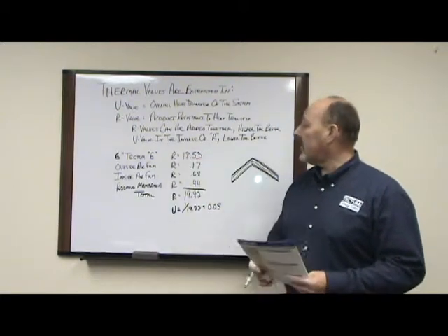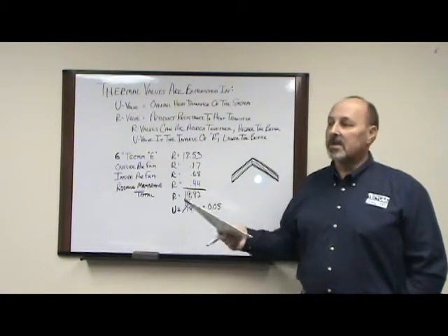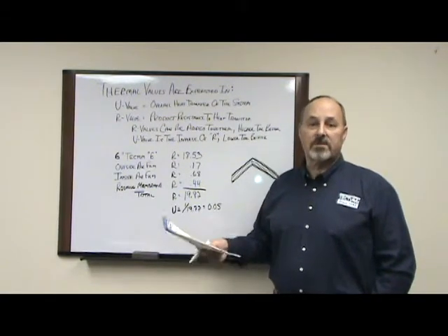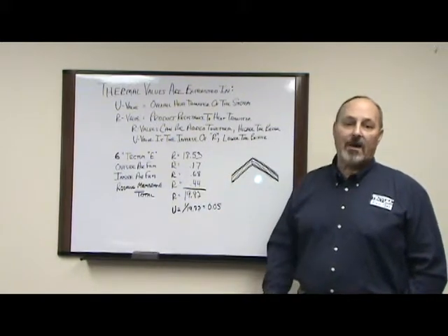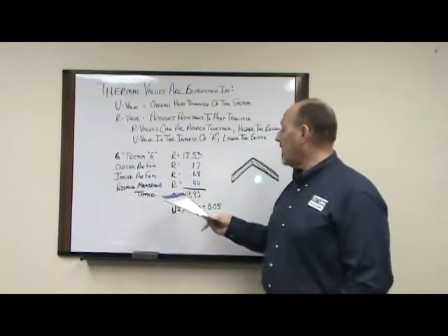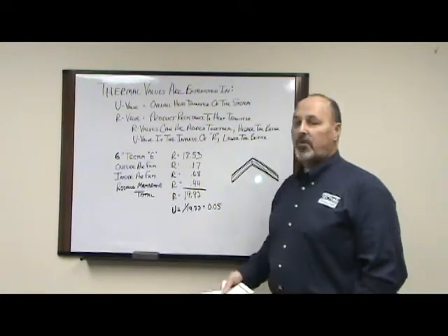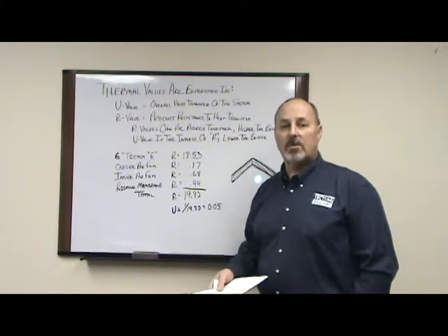But having the R of 18.53 by itself does not meet some of the requirements of the R value of 20. But when you add the inside and outside air film and the roof membrane, you will get to the R value of 19.82, or 20, which is many of the code standard requirements.